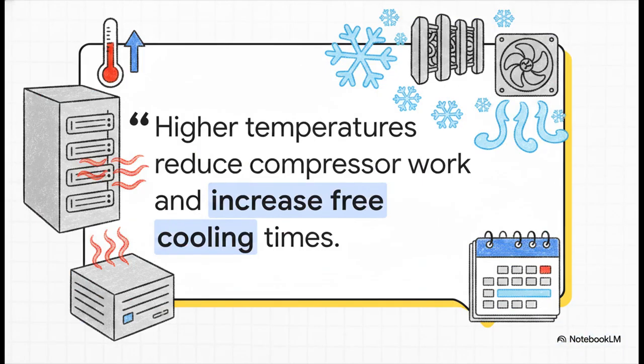And here is the paradox. Higher chilled water supply temperatures actually reduce compressor work. It significantly increases free cooling operating hours, which maximizes the utility of air-cooled free cooling chillers. Basically, hotter servers make cooling more efficient because facilities can just turn off their compressors and rely on outside air for much longer portions of the year. It's a real game changer.